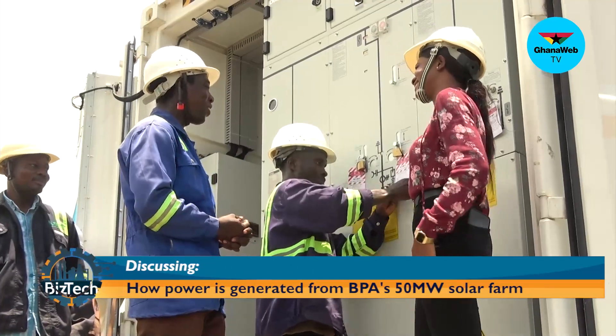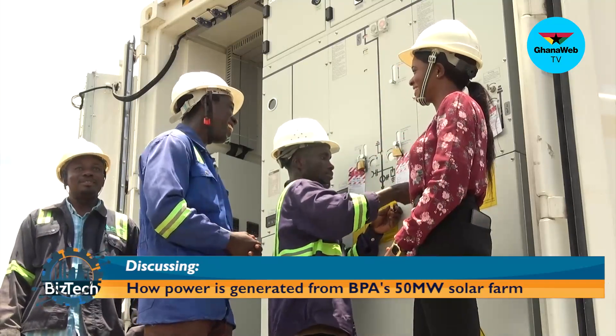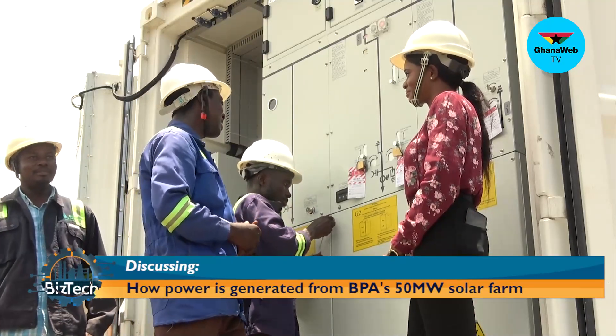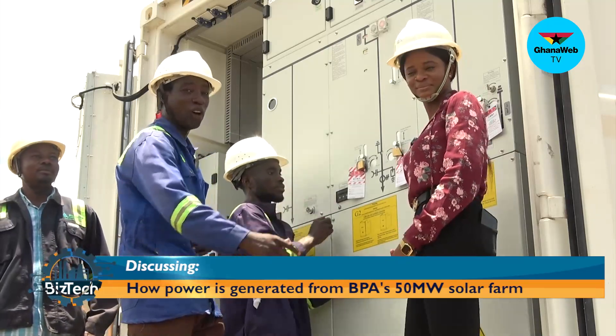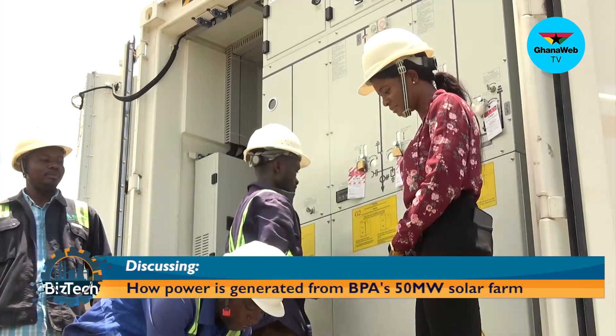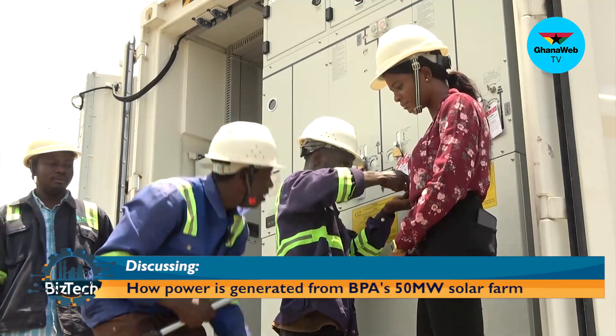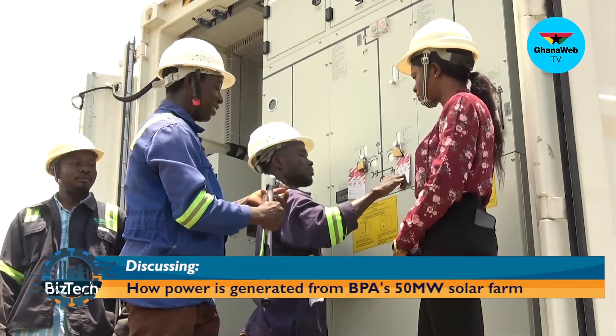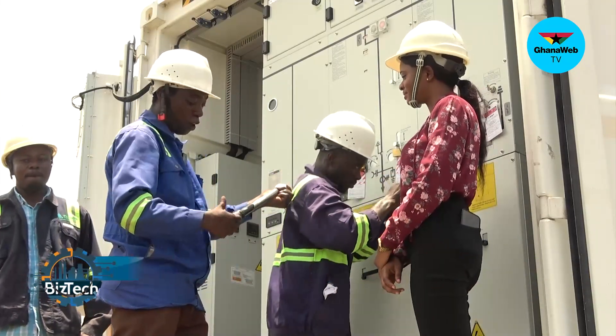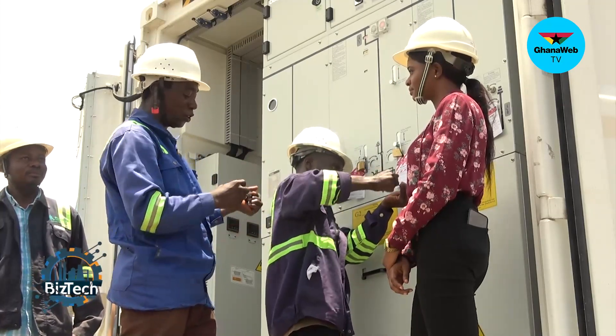How tough is your job? I know every job is tough, but it involves a lot of energy to strike the bolt. It's not easy because we use the torque equipment. We set it around 45 Newton-meters, then you press it softly and turn it. If you are not able to set it well, the bolt will cross-thread. So we are very, very cautious when we are setting it.